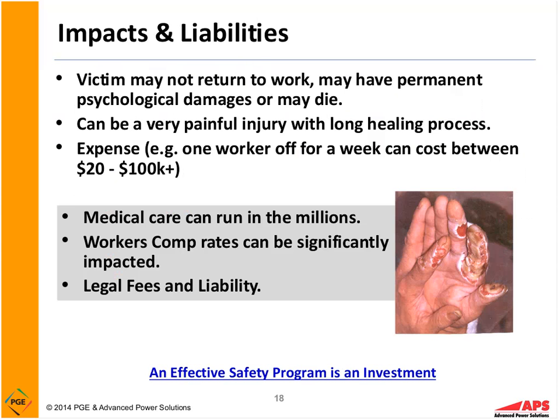So when we look at impacts and liabilities of an arc flash incident, the victim may not return to work, may have permanent psychological damages. These can be very painful injuries. And the expense of a worker being off for a week, according to the risk and loss prevention folks that I talk to, can range from $20,000 to over $100,000. So you can see that we're talking about a significant amount of money, plus a worker can be impacted for the rest of their life. They may not even be able to come back to work. So an effective safety program is an investment.